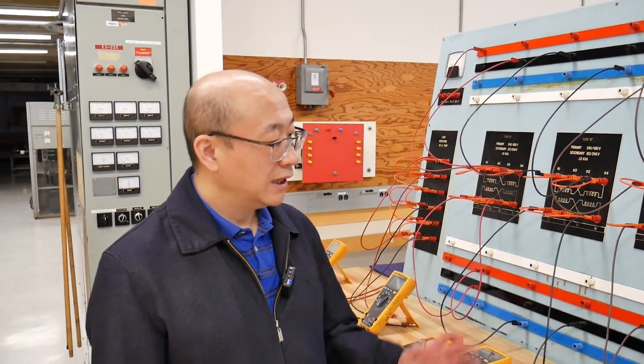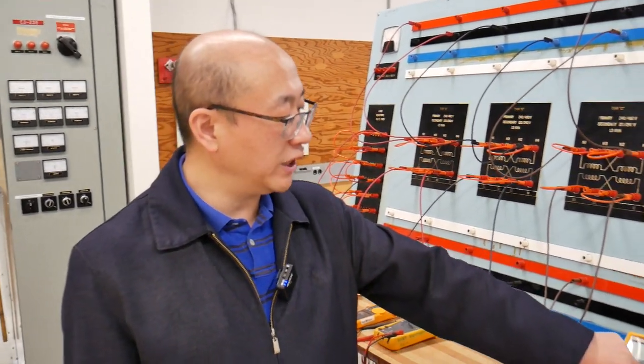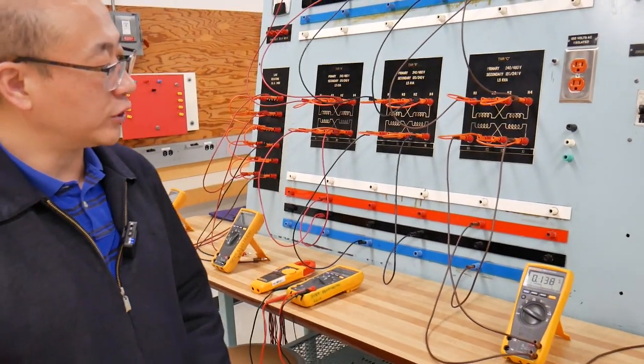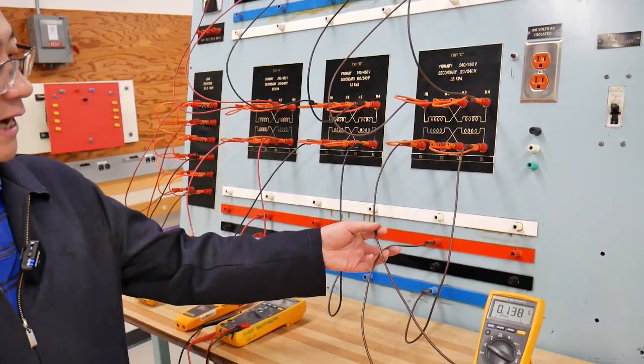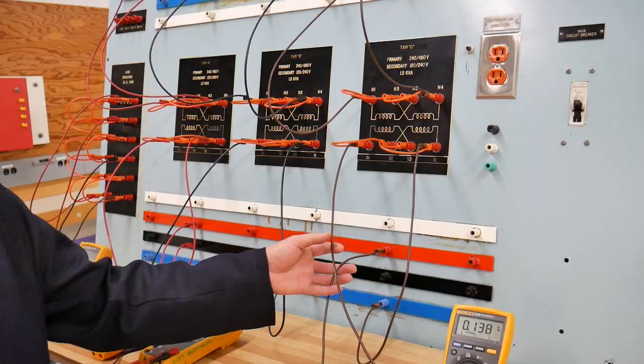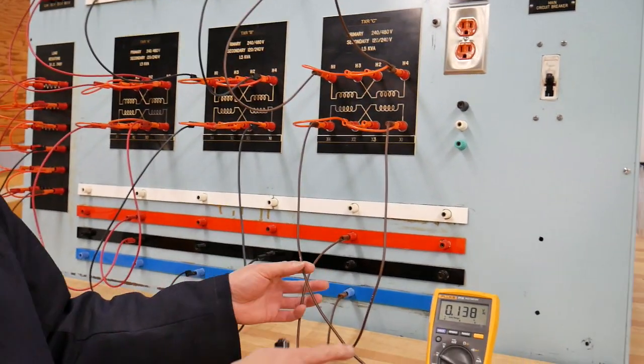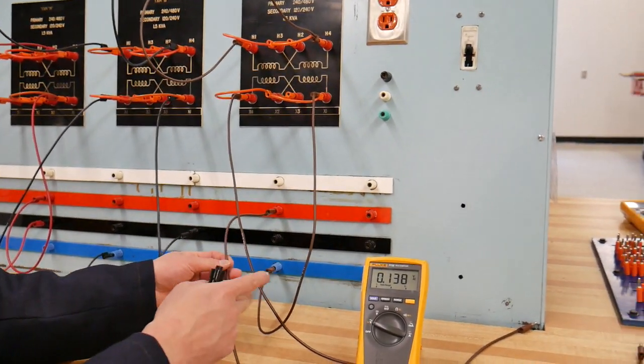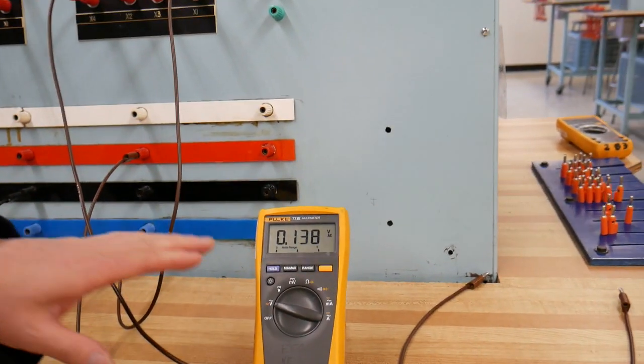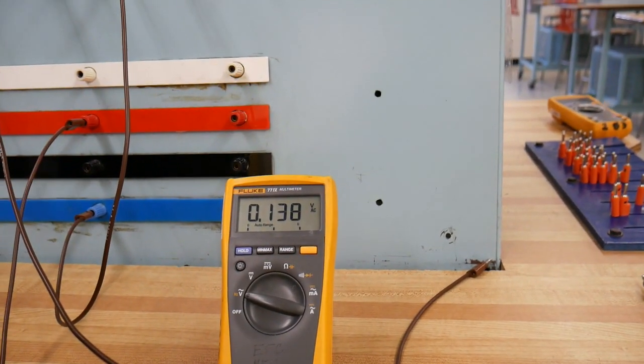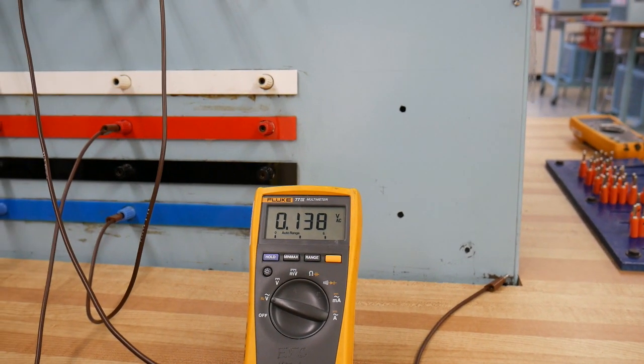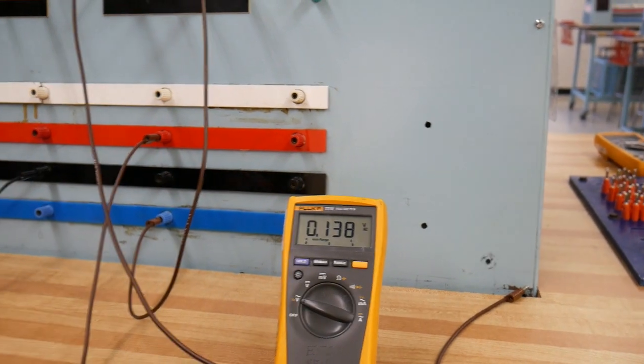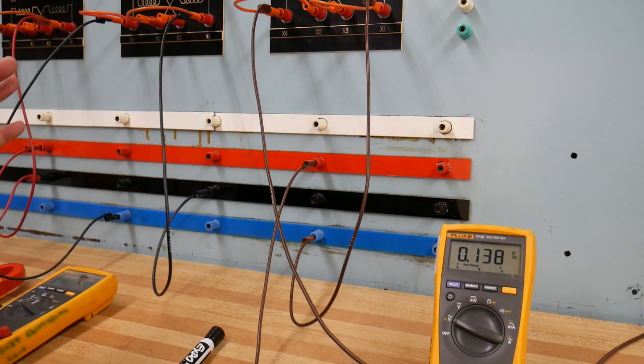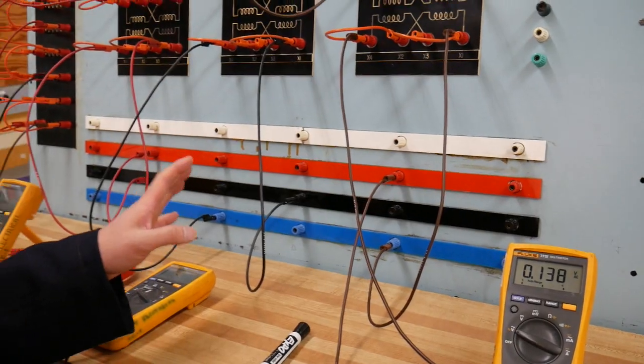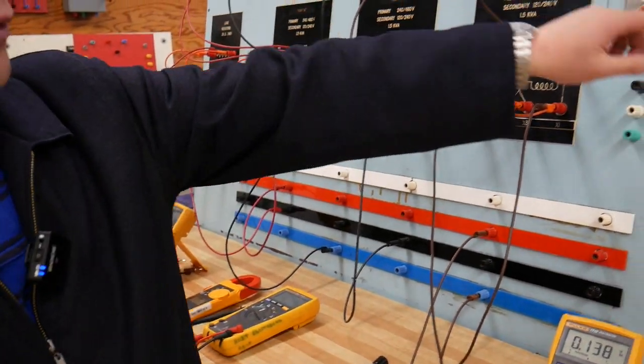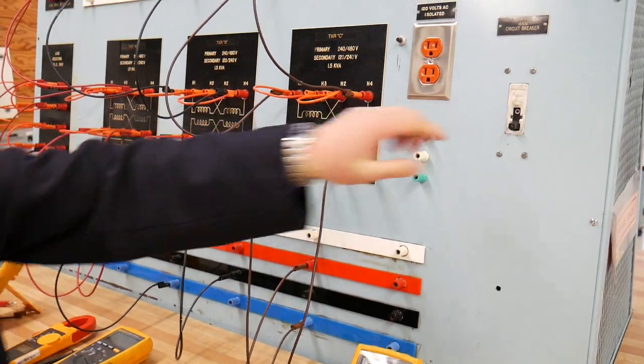Okay, so the first thing I'm going to show you is the delta closure test. This is the last jumper for the transformer. I didn't connect it, I put a voltmeter there instead. This voltmeter gave me a reading of about 0.13 volts, which is the correct voltage. I want to measure close to 0 volts. But if I redo the connection on the transformer, you'll see what this voltmeter reads.